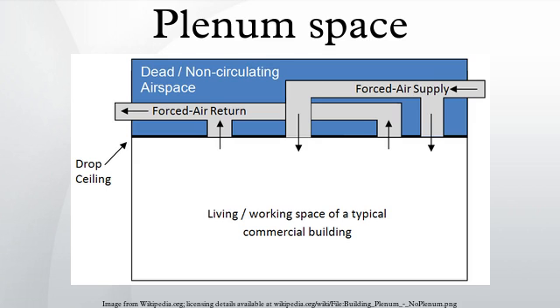A plenum space is a part of a building that can facilitate air circulation for heating and air conditioning systems, by providing pathways for either heated, conditioned, or return air flows, usually at greater than atmospheric pressure. Space between the structural floor and the dropped ceiling, or under a raised floor, is typically considered plenum.